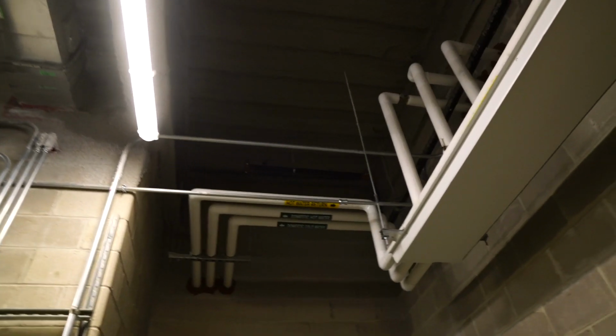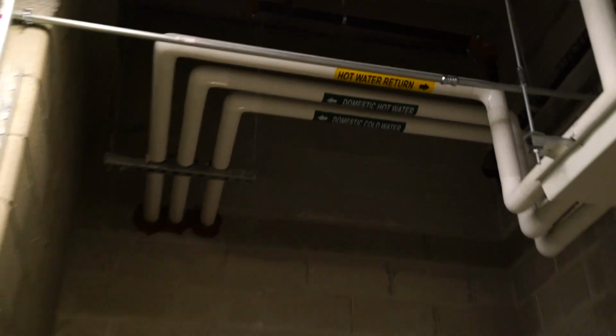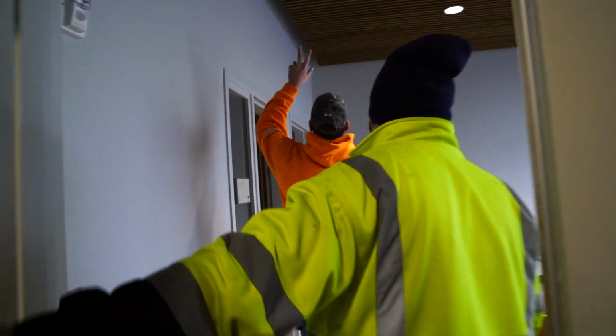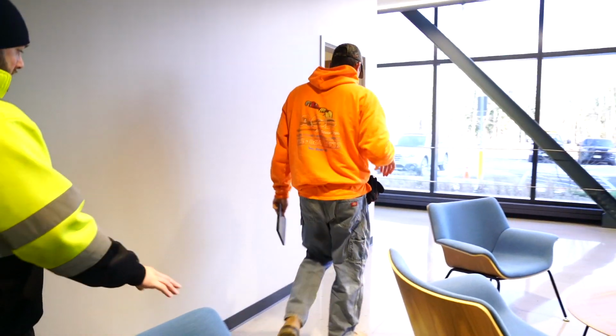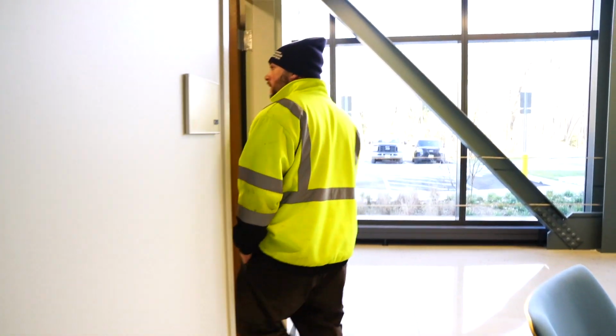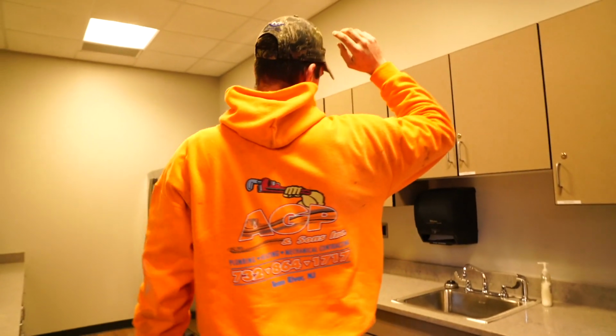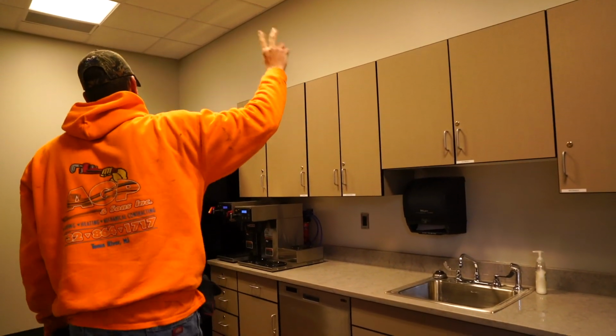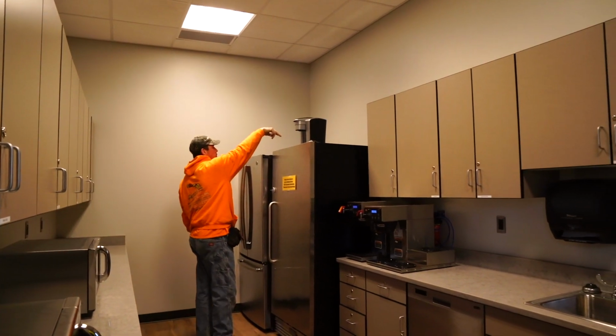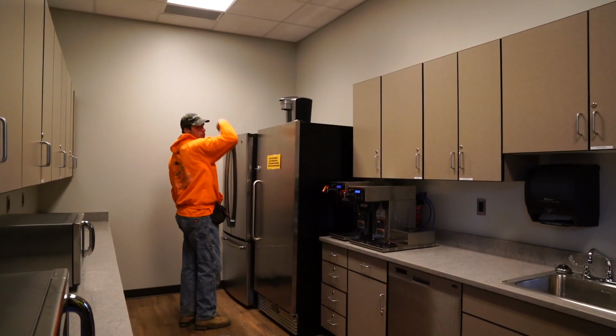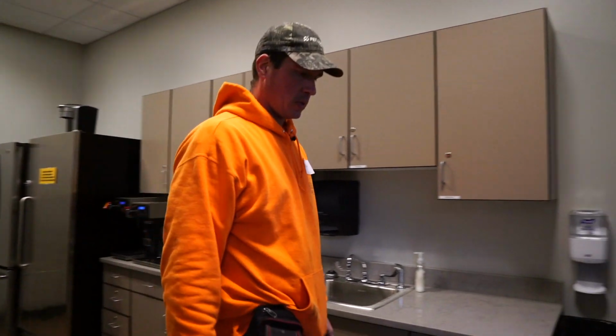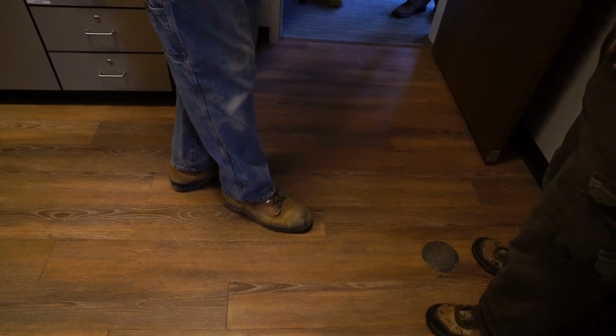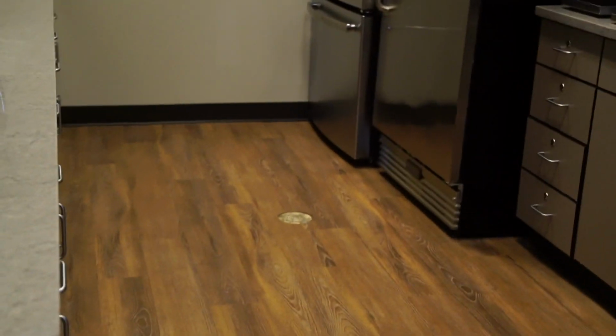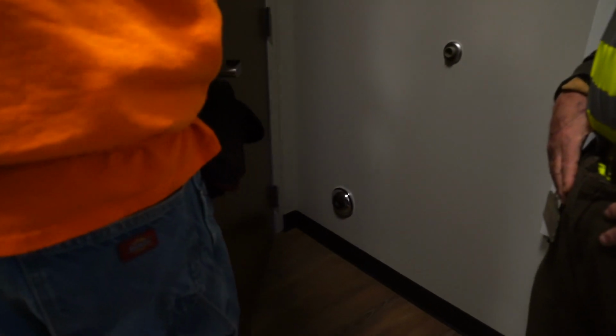To feed the little bit left on this side of the building, 3 lines, domestic cold, domestic hot, return. They are right overhead here. They go through this wall. They come through right overhead. You have cold and hot feeding your sink. Isolation valves are overhead. Then you have 2 cold lines that go to your ice maker feed lines in the wall here. Valves overhead. Same thing, another clean out right there. Clean out right there, sanitary system. You also have a clean out behind the wall here. And that picks up.